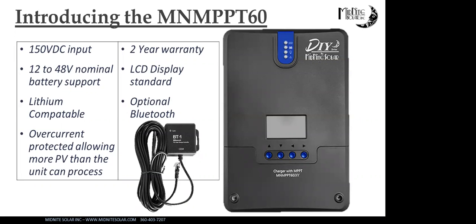We had one charge controller that was massively overvoltaged, which isn't the charge controller's fault. We had one where the display didn't work, which is a defect. Then one inverter had nothing come up on the display, but we found updating the firmware fixed it. And one inverter had the aux relay for the gen start get stuck—it basically welded the relay. I'm still suspicious the installer may have tried to run too much current through it, since it's just a pilot relay. But that's it—for over 1,000 units out the door, those are the 4 we've had any problem with.